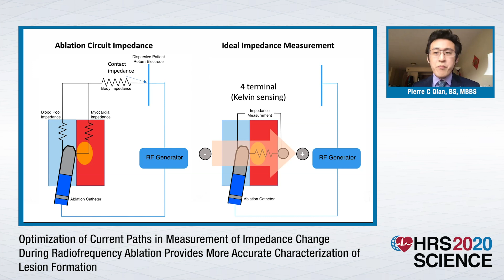However, circuit impedance drop has only a modest correlation with lesion dimensions. This is due to many components that contribute to circuit impedance other than myocardial impedance alone, such as the blood pool, body tissues, and contact impedance at the patient return electrode. A better way of obtaining a measure of myocardial impedance change would be to place a second electrode to direct the measurement path through the region of heating, independent of the ablation circuit. Even better would be to have a set of current injection electrodes separate from the measurement electrodes in order to eliminate electrode contact impedance in the measurement.